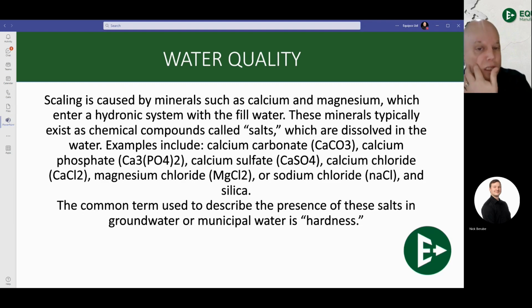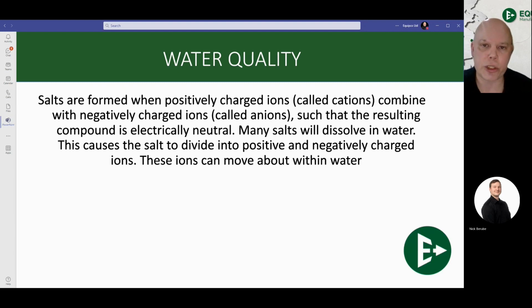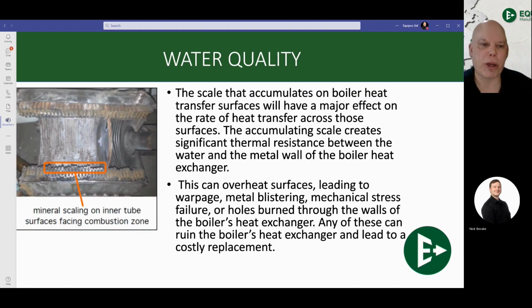So if we have hardness inside of a system, or hardness in your water, we got to get that out somehow, because if we don't get it out before it goes into the water in the hydronic system, it's going to come out as soon as we turn the hydronic system on. And that is not what anybody wants, because that's going to lead to a low flow application. So this is basically just talking about how they kind of come to be, positively and negatively charged ions, and how they will stick to each other and start to create more and more abundant little deposits as these little ions move about inside the water, and how that sticks to the inside of these heat exchangers.